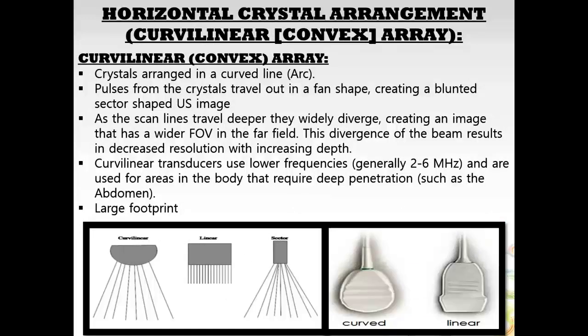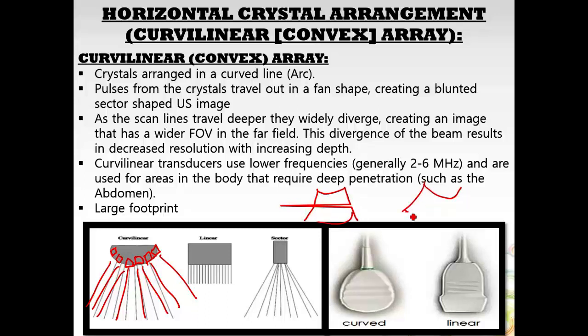Next is our curvilinear array. These are also called convex array. And with these, the crystals are arranged in an arc or a curve. So you have your crystals here. And as the crystals fire, they go out in kind of a fan shape. And this is what gives us our field of view, our sector field of view. So with a curvilinear picture here, we get a sector shaped field of view. So just like this. Curvilinear arrays are lower frequency transducers, anywhere generally from 1 megahertz to about 6 megahertz.